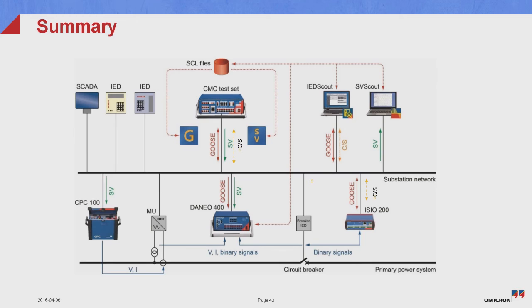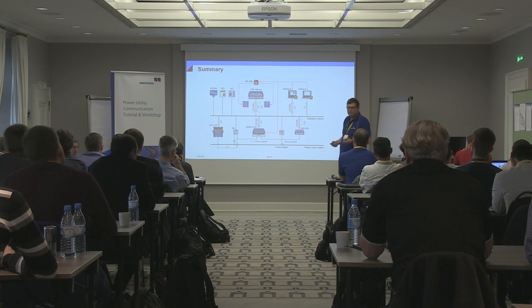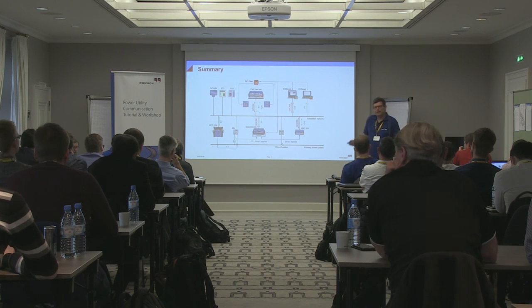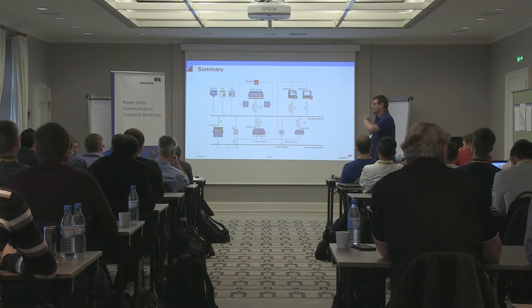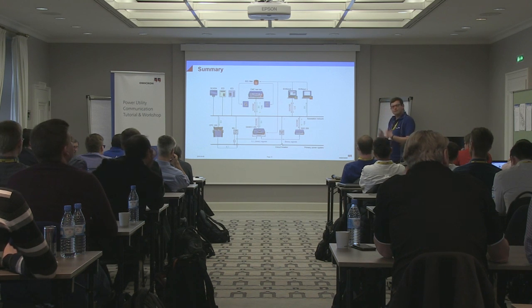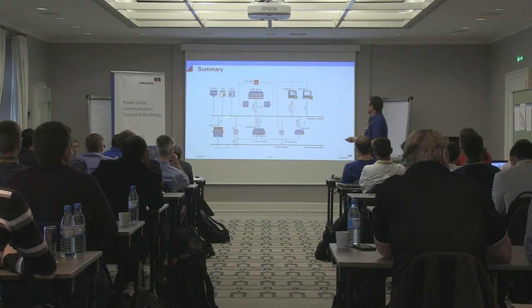Good. Just to summarize this picture again, there are a lot of different tasks that can be done. We could not cover everything here in the 35 minutes. There's also the possibility, for instance, that you can do primary injection, because if you don't believe in what is happening, the last possibility is all the time to try it out with primary, so really inject the current and then check what is happening with the sampled values that you receive afterwards. So that's why we also have the possibility like that.